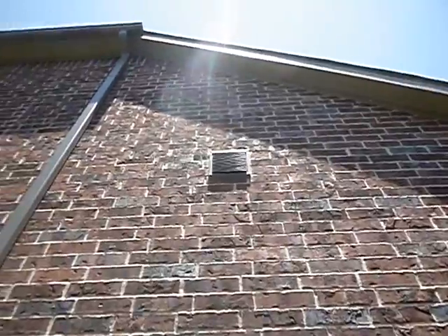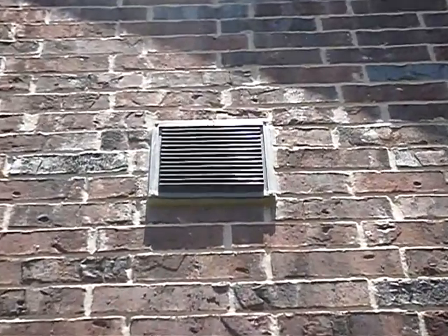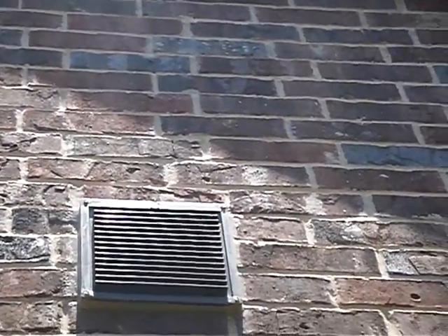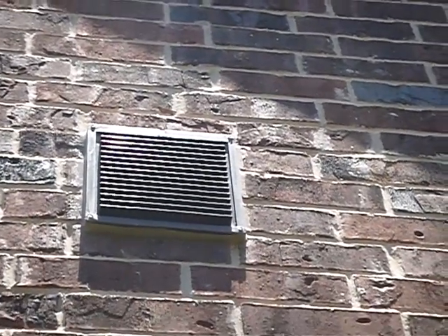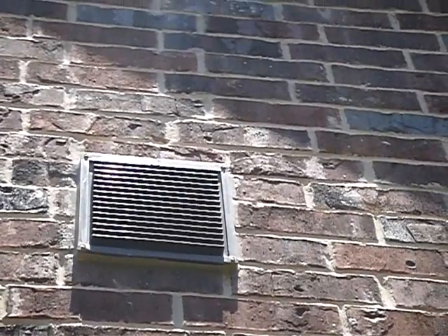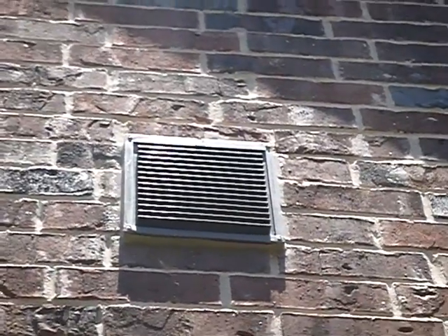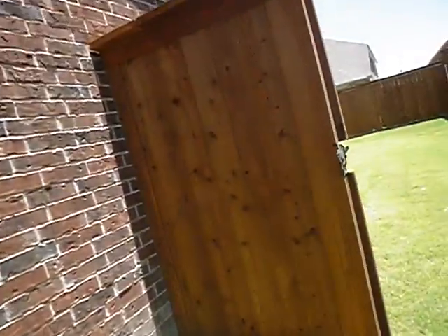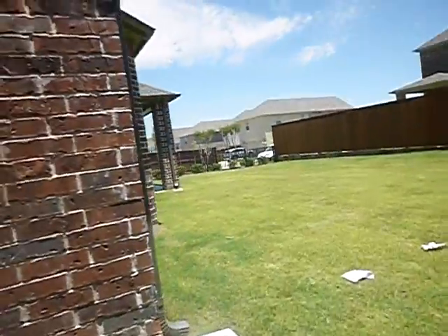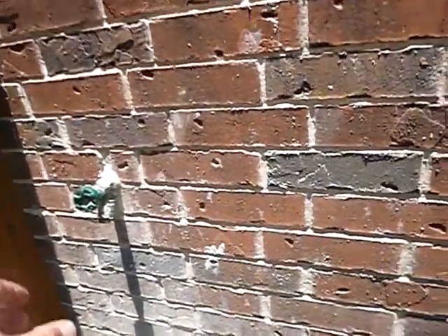This is the fresh air induction fan. This is a very tight house, very tight - the attic is not ventilated. I'm quite sure once I get into the attic I'll see open cell foam on the decking. So this house is like a jar, airtight like a jar. And like you poke holes in the top of a jar so a praying mantis can live, that's basically what this is. It lets a certain amount of air into the house where it's conditioned, hopefully filtered, and hopefully goes through a heat exchanger. There's passive conditioning, but it goes into the house so you always have a fresh air exchange, always some fresh air in the house. That's good, we want fresh air, everybody wants fresh air.